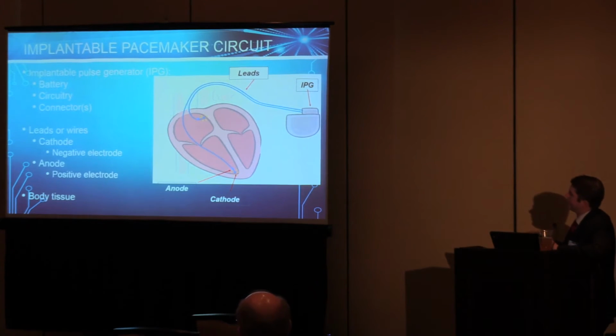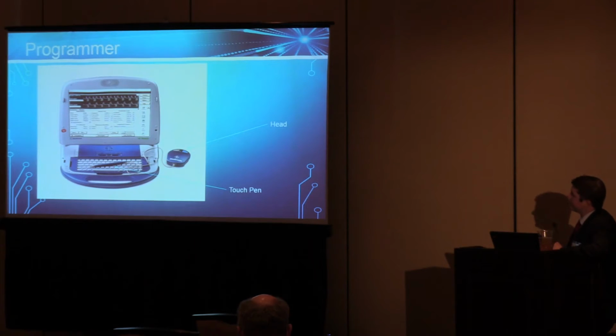So again, just to go through the components of the pacemaker, we have the pulse generator. Again, this is the brains of the unit, and it also contains the battery and the electrical energy which is used to pace at the tips of the pacing leads in contact with the myocardium. Again, anode and cathode. We worry sometimes about having anodal or positive electric capture. But that's something we can sort out separately for you. Just so you know, those are the components of the pacing system.